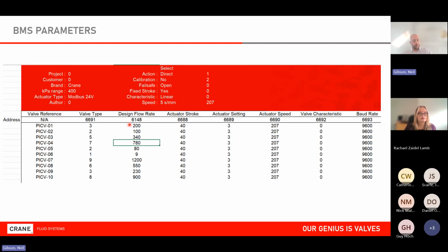As we all know, Modbus tables can be long, complicated, and challenging to read. So what we've done, because we typically size the PICV and the valve, is we have all of the information such as flow rate, size, and range, and we can input that into a selection software, and based on those values generate the required numbers under the Modbus addresses as well. So if I was to give an example, and I've just picked some random valves here, PICV number 1 to 10. If I needed to input a flow rate of 0.2 liters a second, I now know that PICV number 1 under address 6148 needs a value of 200 via the BMS. Valve number 2 requires a value of 100.